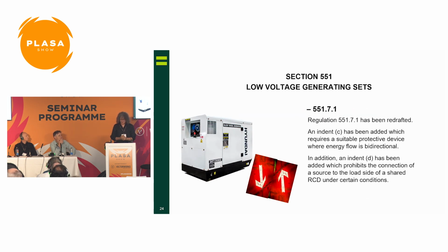On to generating sets - this is an interesting one because the arrows indicate we're now talking about bidirectional devices. Conventionally, you might have a utility supply into a building, and then a battery storage, or a generator that's contributing to the system, operating in parallel. It's not about current flow so much as energy flowing in different directions, but you've got sources essentially on both sides of protective devices.